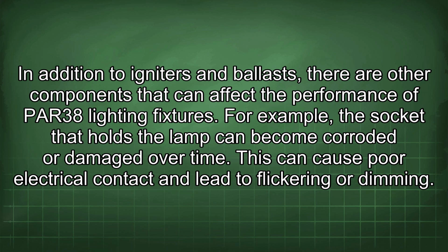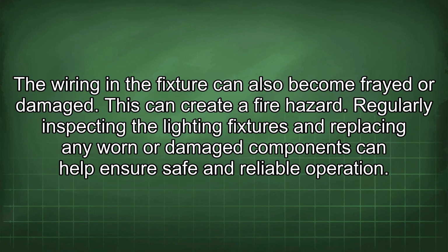In addition to ignitors and ballasts, there are other components that can affect the performance of PAR38 lighting fixtures. For example, the socket that holds the lamp can become corroded or damaged over time. This can cause poor electrical contact and lead to flickering or dimming. The wiring in the fixture can also become frayed or damaged. This can create a fire hazard. Regularly inspecting the lighting fixtures and replacing any worn or damaged components can help ensure safe and reliable operation.